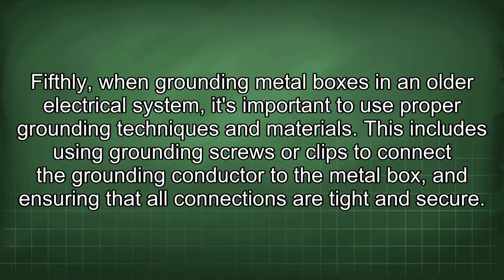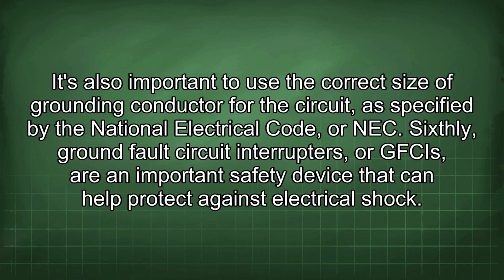Fifthly, when grounding metal boxes in an older electrical system, it's important to use proper grounding techniques and materials. This includes using grounding screws or clips to connect the grounding conductor to the metal box and ensuring that all connections are tight and secure. It's also important to use the correct size of grounding conductor for the circuit, as specified by the National Electrical Code, or NEC.